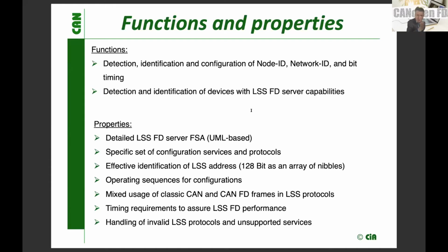Beside that, we have unique identification of devices by their LSS address, consisting of the content of object 1018. Then we have operating sequences, which say how I handle the LSS configuration of a device, how I handle address configuration, identification, and the same for bit timing.